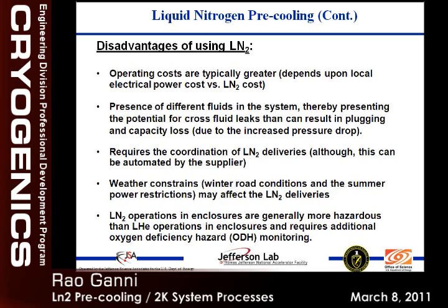We had it only once after I came in the 90s. At some point, because of the power, the nitrogen plants negotiate the power. If there is a peak power demand, they will be asked to shut down to get a much more favorable rate for their electric bill. So at that time, they shut down our nitrogen. So we borrowed from NASA. So we were subjected to it once in my 16 years here. And generally now we have to deal with ODH issues, because you can't differentiate nitrogen from air if there is too much of it, and you can get into safety issues. So these are the disadvantages.